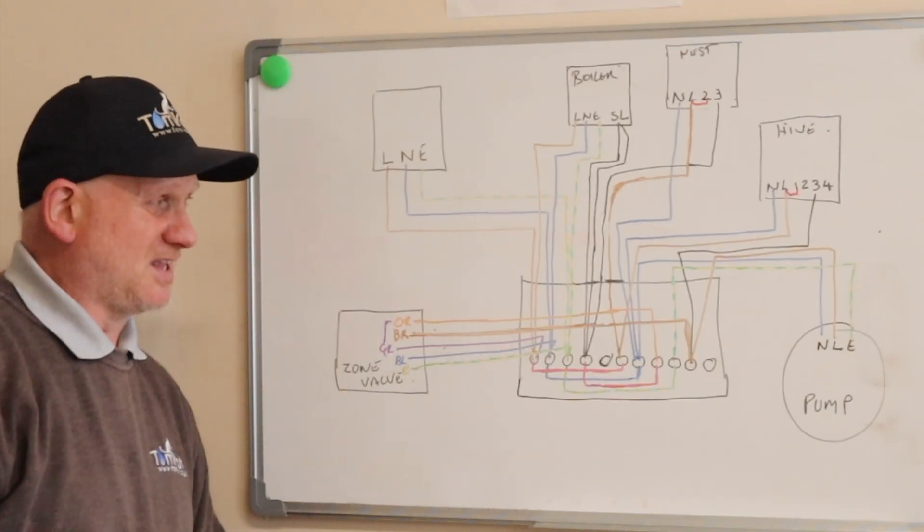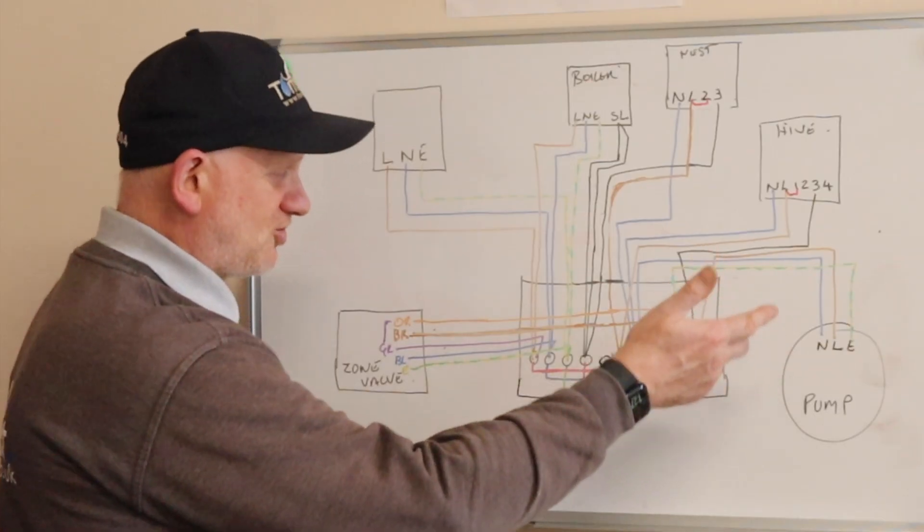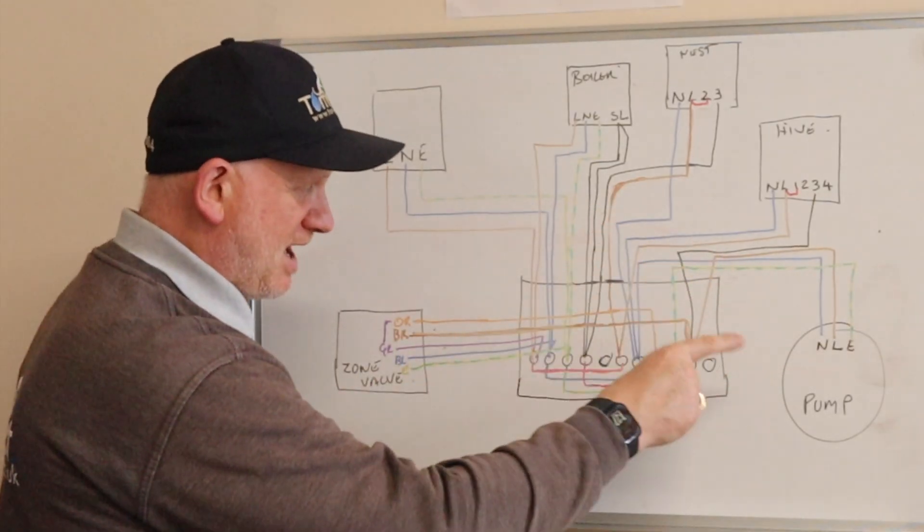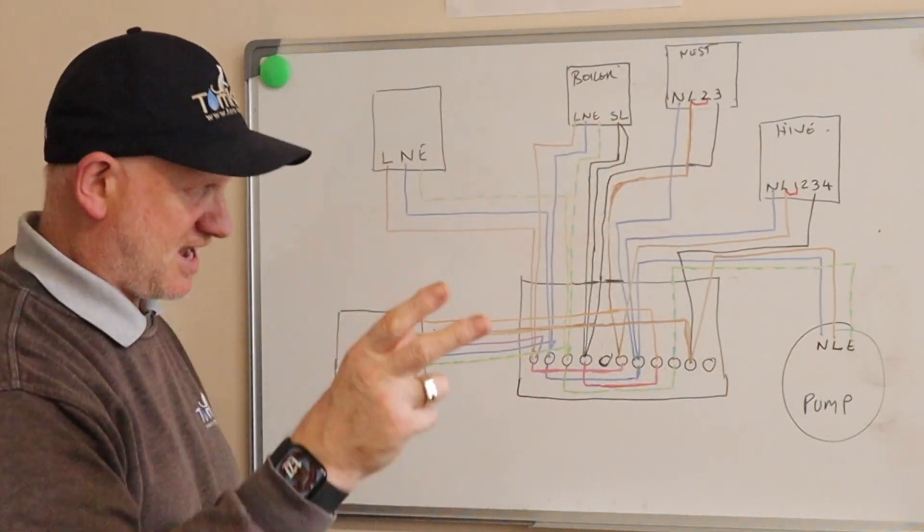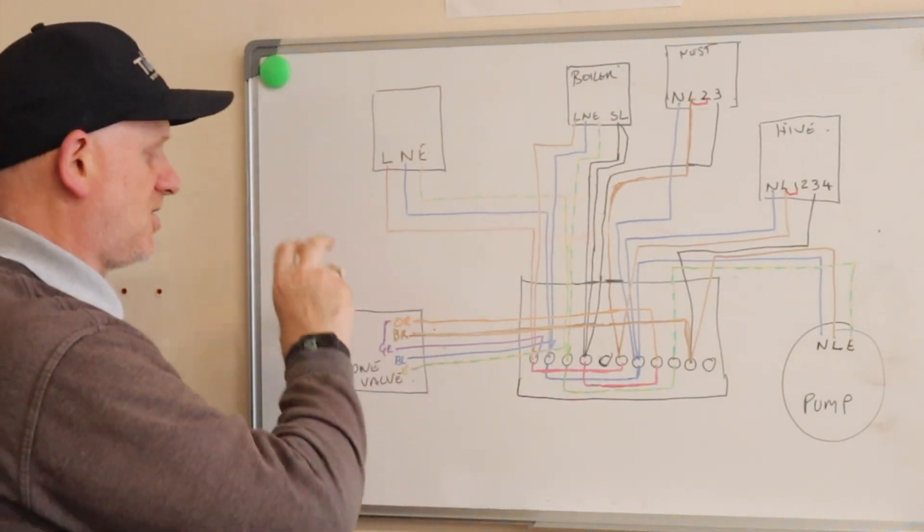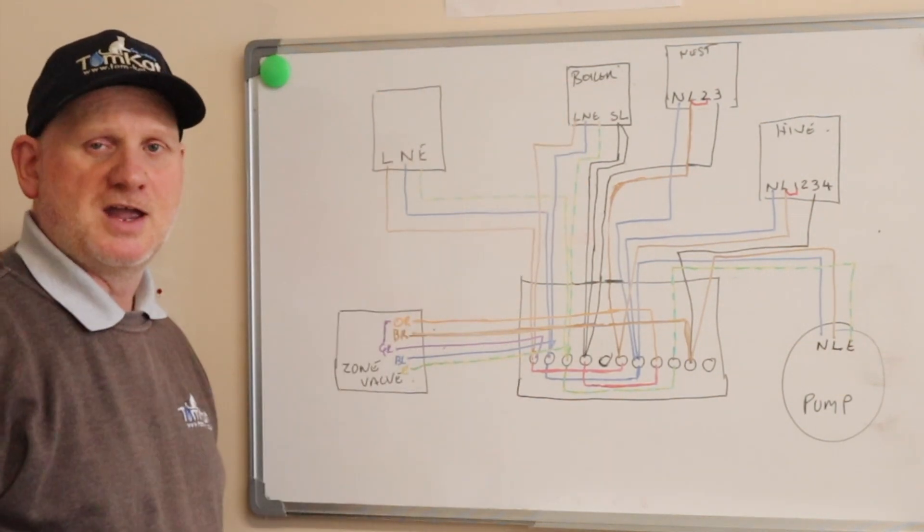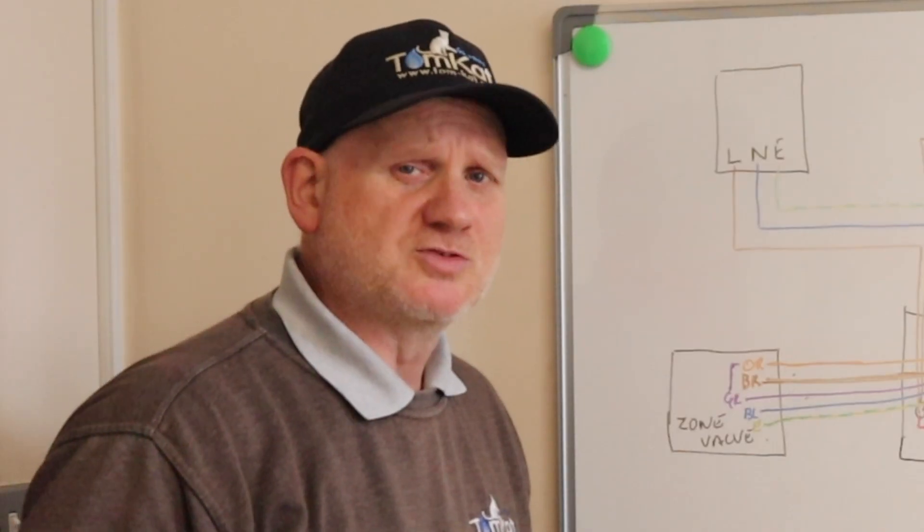So that's basically how I wired it up. Neutral and earth for the pump coming from here. The power for the pump was actually coming from the stat. So as the stat was made it brought the pump on. It also operated the zone valve and it was the zone valve which brought the boiler on. Hopefully that makes some sense.